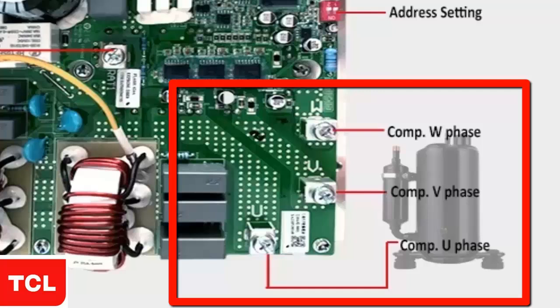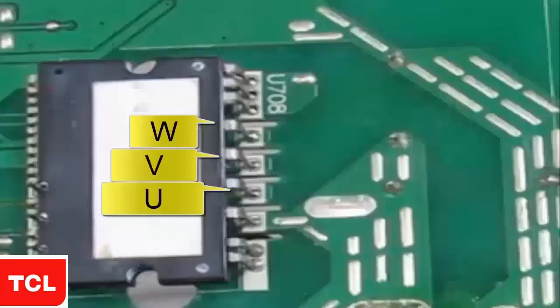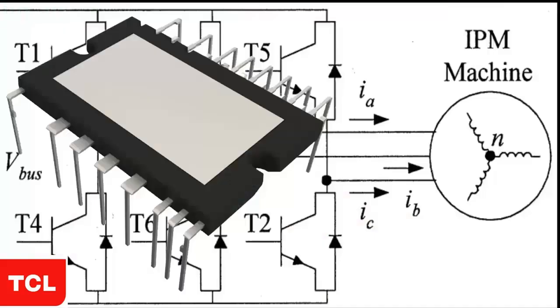Set the multimeter to the diode scale. The IPM electronic circuit is internally composed of six IGBT transistors, each containing a diode that we will test. Let's start with the integrity test of the first three diodes.